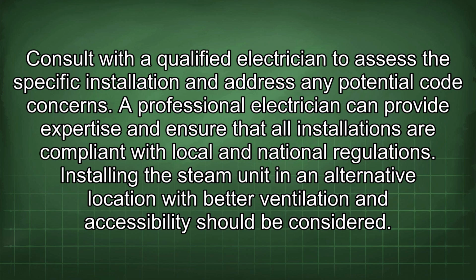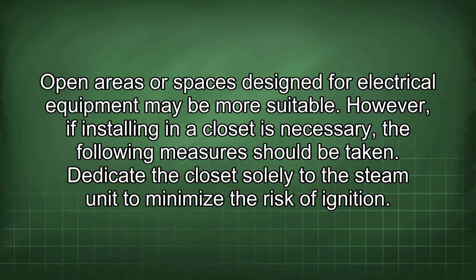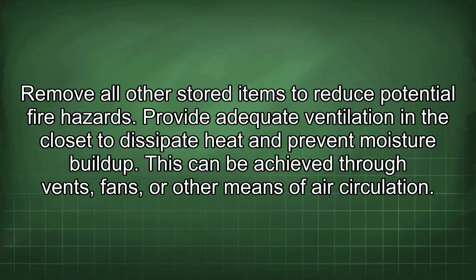Installing the steam unit in an alternative location with better ventilation and accessibility should be considered. Open areas or spaces designed for electrical equipment may be more suitable. However, if installing in a closet is necessary, the following measures should be taken. Dedicate the closet solely to the steam unit to minimize the risk of ignition. Remove all other stored items to reduce potential fire hazards. Provide adequate ventilation in the closet to dissipate heat and prevent moisture buildup. This can be achieved through vents, fans, or other means of air circulation.